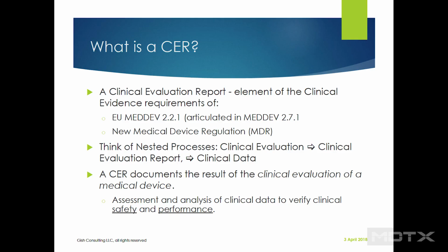Again, the requirements. So MedDev 2.7.1 articulates the clinical evaluation requirements. I don't know how many of you are versed with European directives and regulations, but they're really different than how we do things in the U.S. And so very referential too. Not that the QSRs are not referential for FDA, but I find EU regulations exceptionally referential.